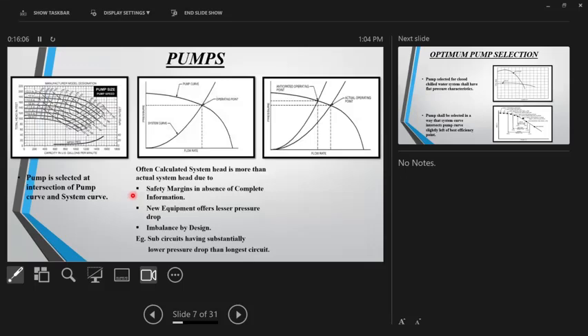Now, we will start discussing a few equipment. Obviously, the pump being the most critical. When you select a pump, you have almost certainly seen a pump curve, which is something like this. On the y-axis there's the pressure, and on the x-axis there's the flow rate. So you would see a pump curve like this.